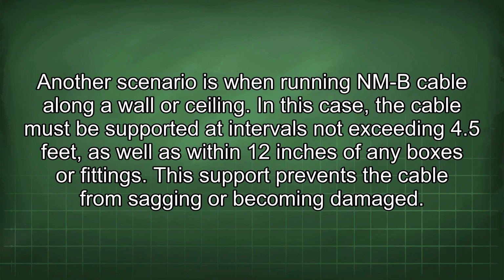Another scenario is when running NMB cable along the wall or ceiling. In this case, the cable must be supported at intervals not exceeding 4.5 feet, as well as within 12 inches of any boxes or fittings. This support prevents the cable from sagging or becoming damaged.